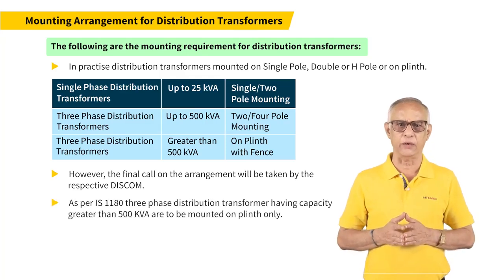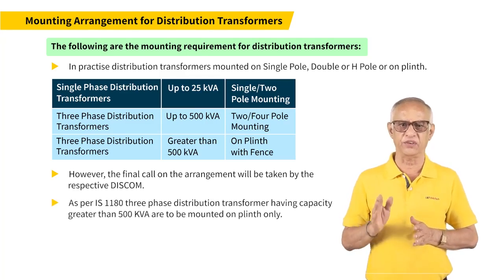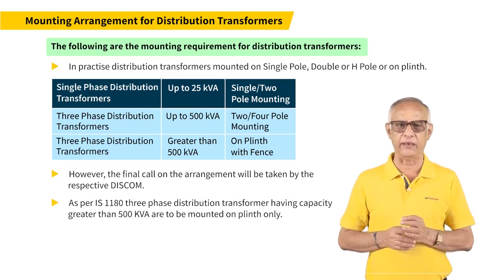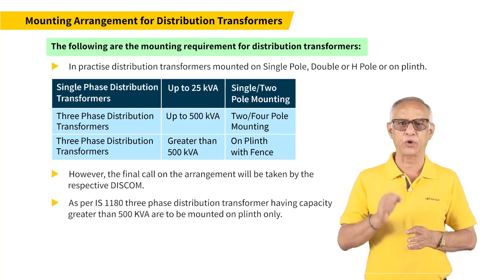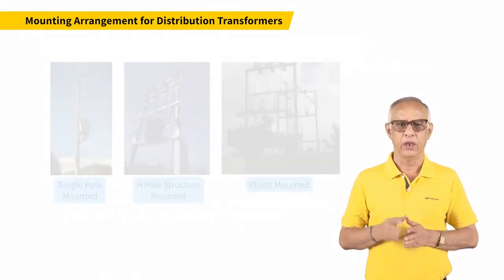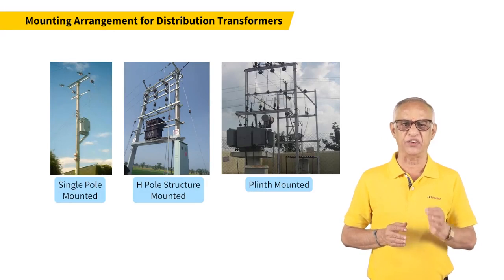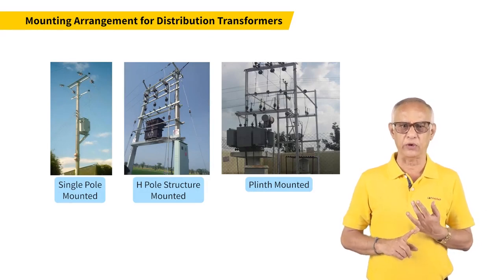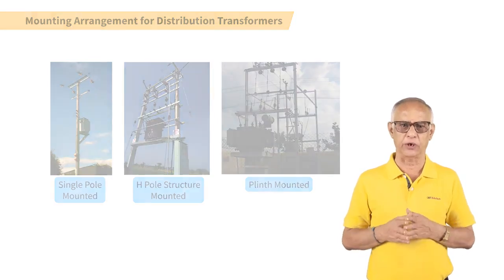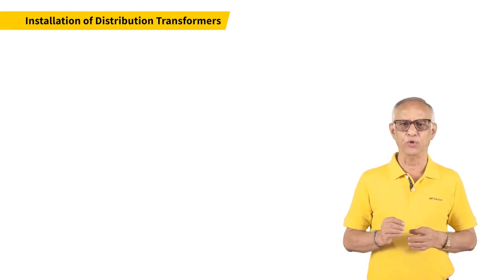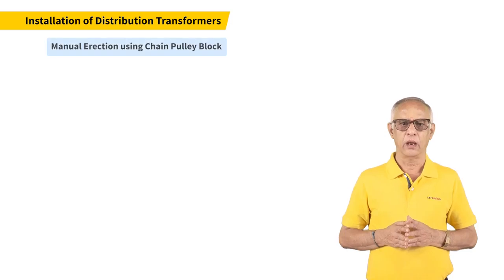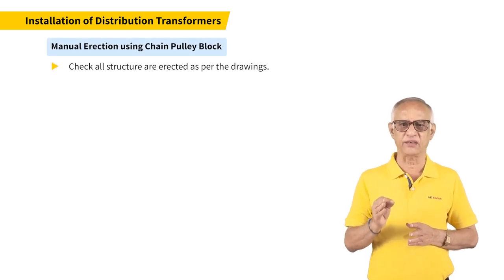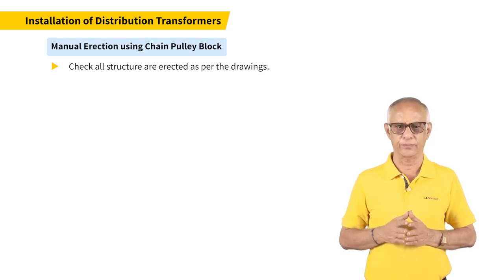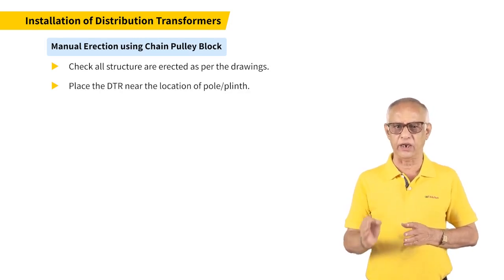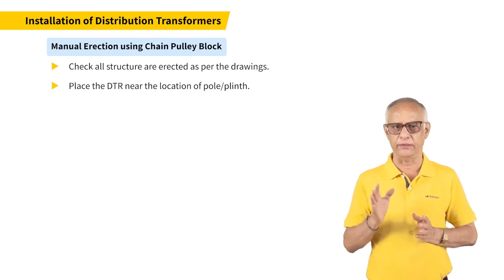As per Indian Standard 1180, three-phase distribution transformers having a capacity greater than 500 kVA are to be mounted on plinth only. The images show mounting arrangements for distribution transformers on single pole mounted, H pole mounted and plinth mounted. Let us discuss how to manually erect distribution transformer using chain pulley blocks. Here are the steps. Check all the structures are erected as per the drawing. Place the distribution transformer near the location of the pole or the plinth.